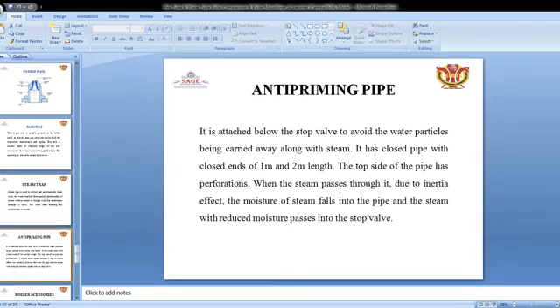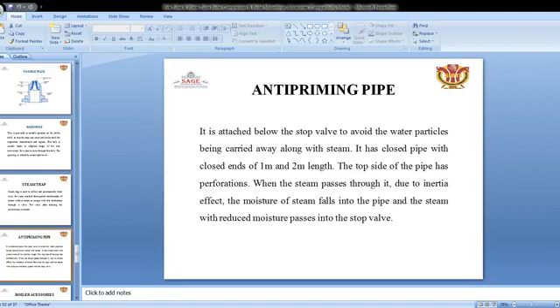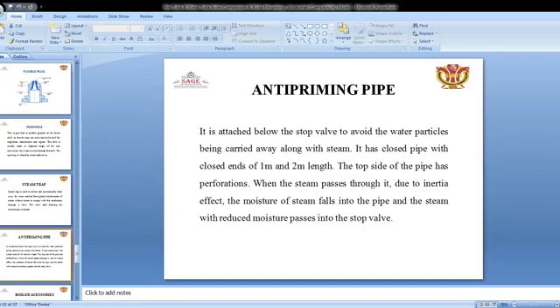The anti-priming pipe is a small device attached below the stop valve to avoid water particles being carried away along with the steam. It is a closed pipe of one to two meter length. The top side of the pipe has perforations. When steam passes through it, due to the inertia effect, moisture falls into the pipe and steam with reduced moisture passes into the stop valve.